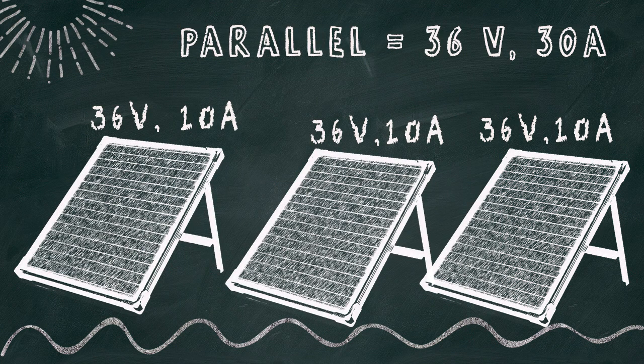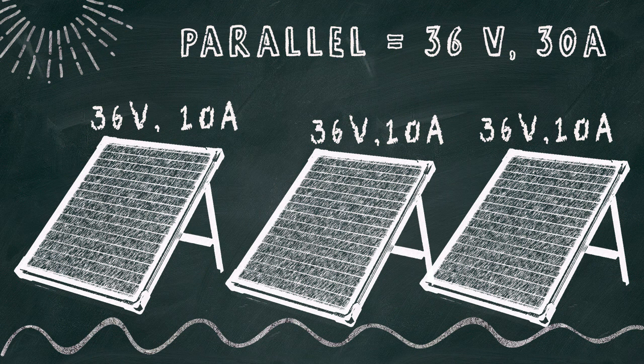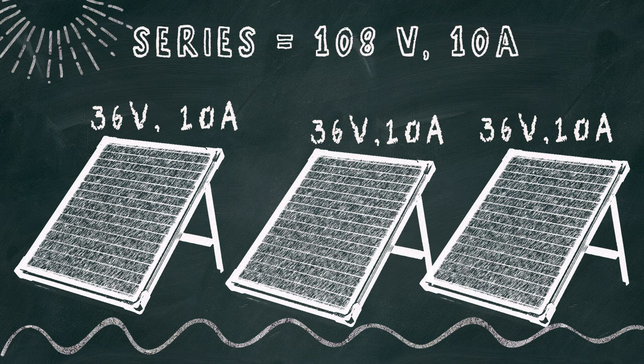Three 360-watt panels of 36 volts and 10 amps generates 36 volts at 30 amps. Total power, a little over a kilowatt. When wired in series, the same three panels produce 108 volts at 10 amps. Power output, a little over a kilowatt.